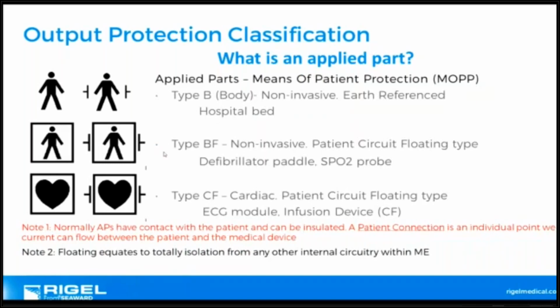These are categorized. In this means of patient protection, we have type B. B stands for body, which is non-invasive earth referenced, so something like a hospital bed, for instance. And this is our symbol for B. We have a little symbol there for defibrillator proof. Then we have BF. That stands for body floating, which I tried to describe earlier on in the slide, where you've got this isolation barrier. So you've got body floating, and we have this guy in the box. And then we have CF, which is cardiac, which is invasive, and has the floating effect too. And this is a much more stringent level. So the pass-fail thresholds for CF are lower than the pass-fail thresholds for B.